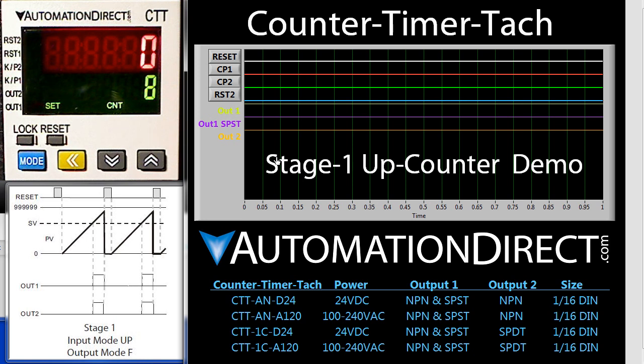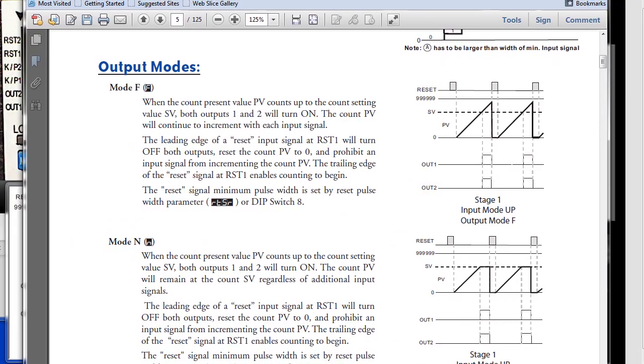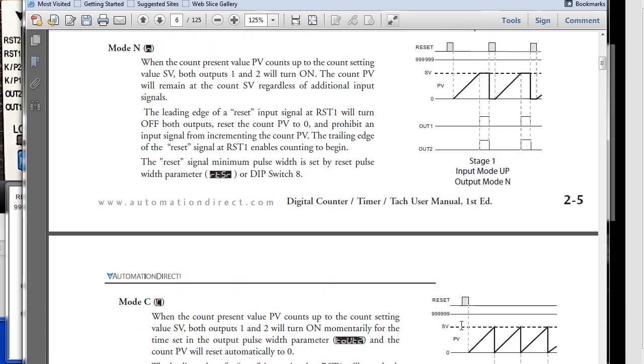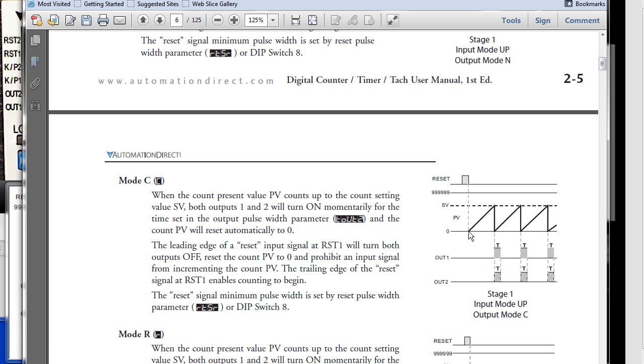What if we wanted to have the counter automatically reset when the set point is reached and not wait for a reset? That's easy – we just go back to the datasheet. We were in mode F and we scroll down through until we find one where the counter counts up and automatically resets when it hits the set point. Here the counter counts up and automatically resets each time it hits the set point. That's mode C.